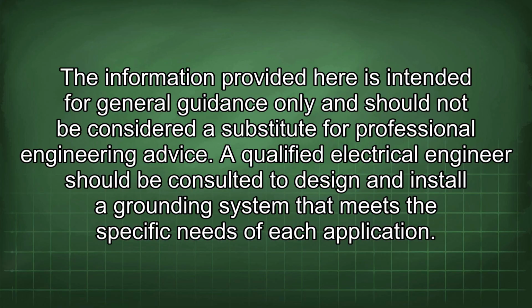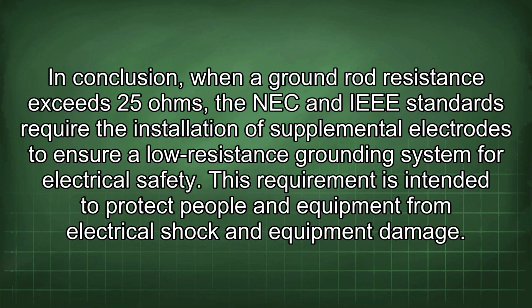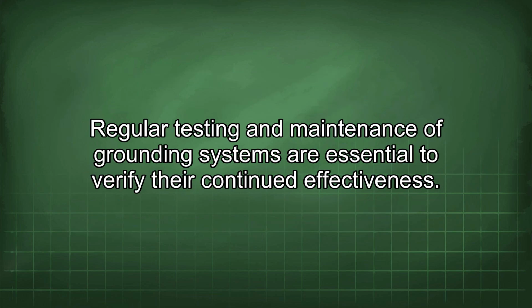In conclusion, when a ground rod resistance exceeds 25 ohms, the NEC and IEEE standards require the installation of supplemental electrodes to ensure a low-resistance grounding system for electrical safety. This requirement is intended to protect people and equipment from electrical shock and equipment damage. Regular testing and maintenance of grounding systems are essential to verify their continued effectiveness.